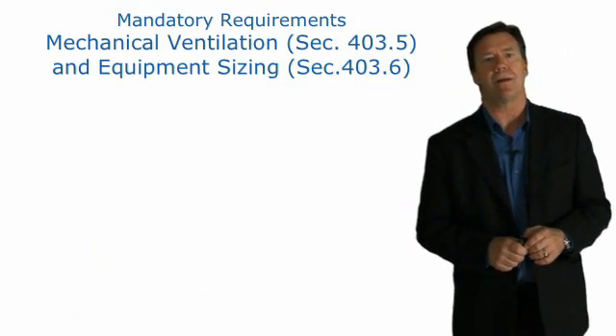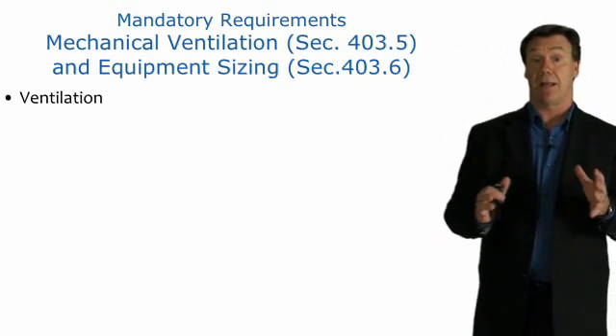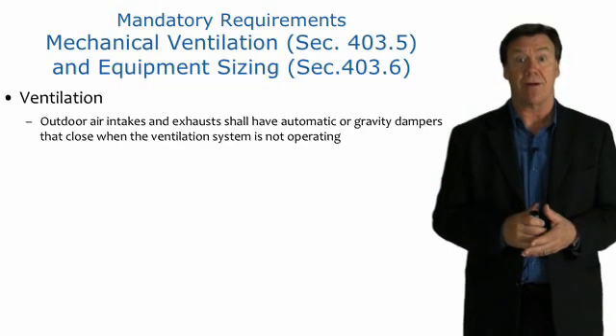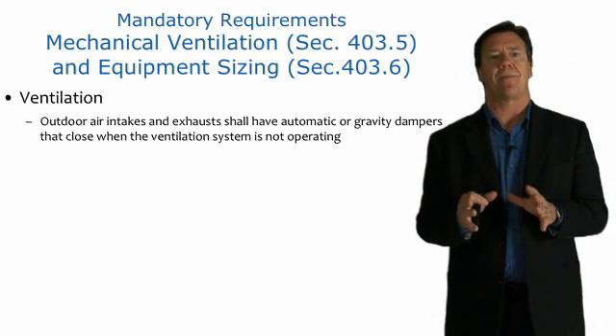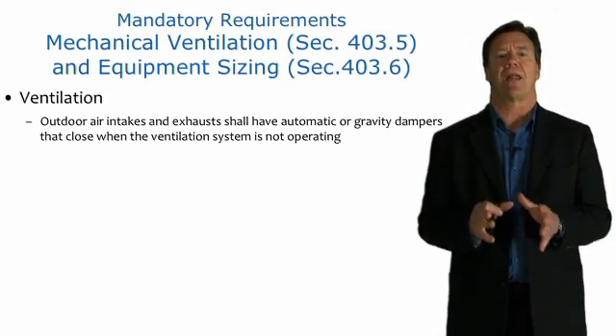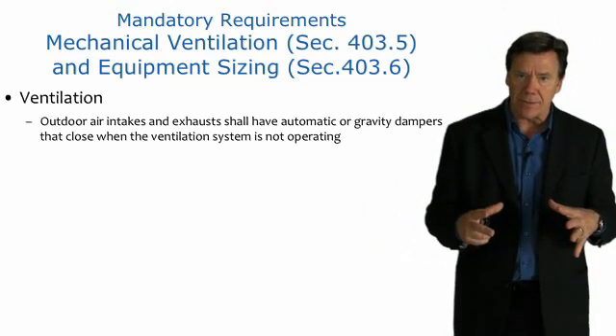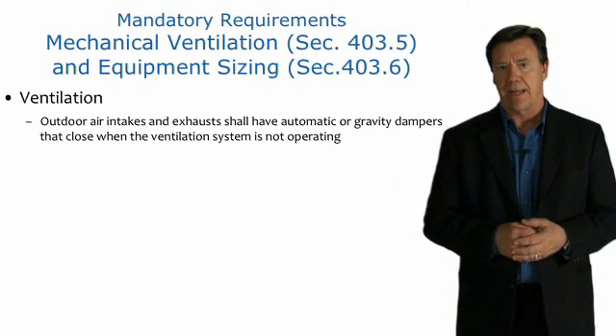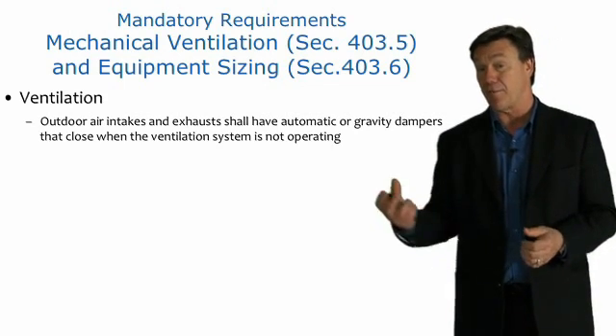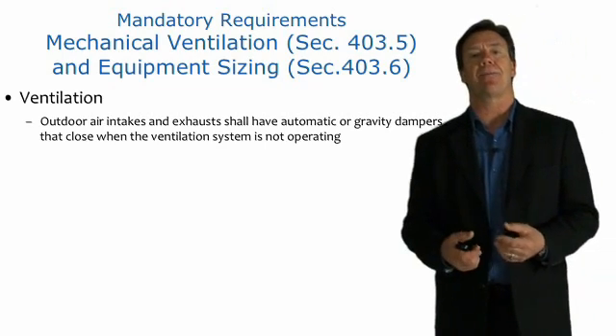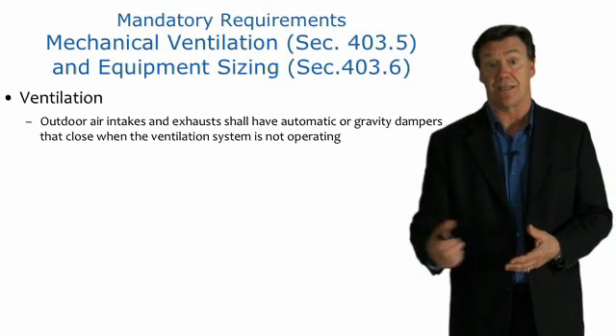Another mandatory requirement is mechanical ventilation. Under section 403.5, ventilation requires outdoor air intakes and exhausts to have automatic or gravity dampers that automatically close when the ventilation system is not operating. As houses are being tightened up, we need fresh air ventilation, but the ductwork providing that fresh air must have dampers that close when the ventilation or HVAC system is not operating.